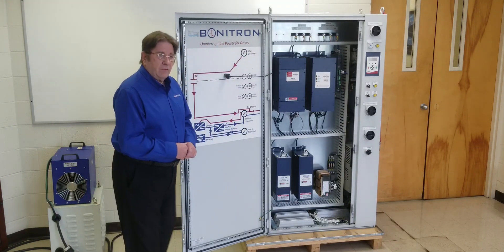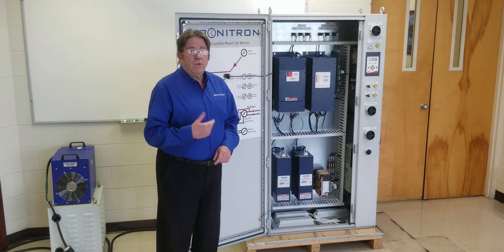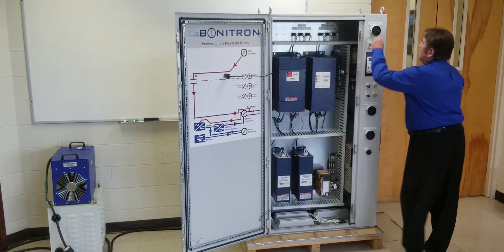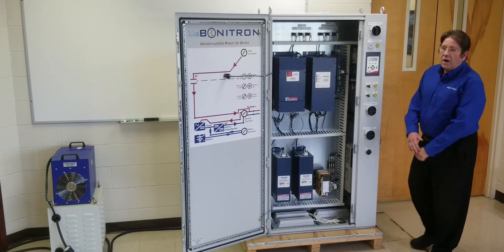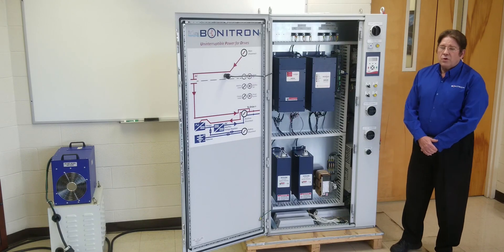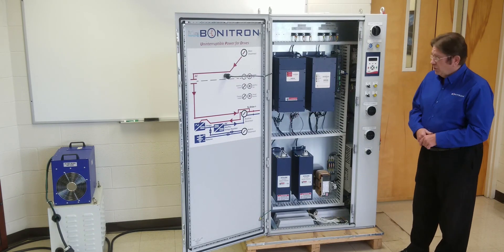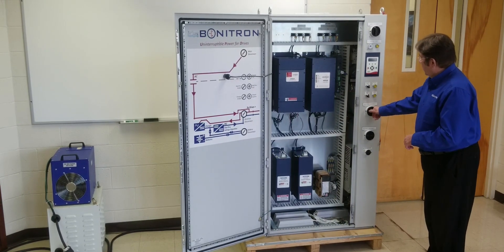Now we're going to energize the system, review the indicators, and then we'll do a ride through test. First we provide power to the drive and we wait 30 seconds for pre-charge. Once we've waited 30 seconds for the drive to pre-charge, then we energize the Bonitron ride through.